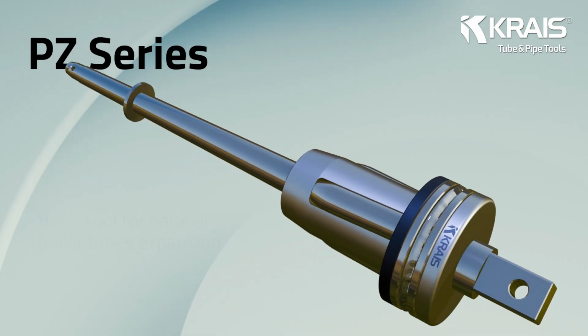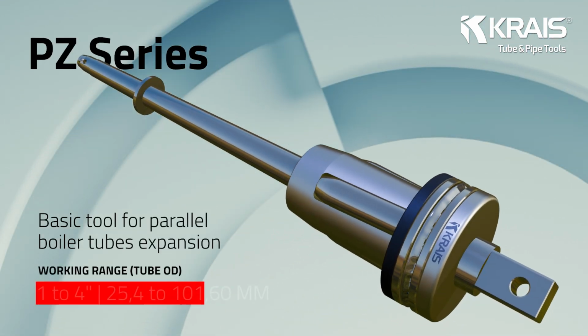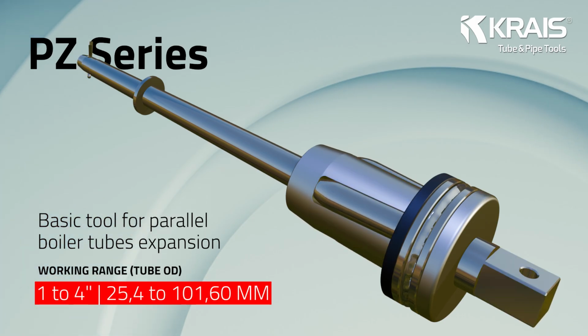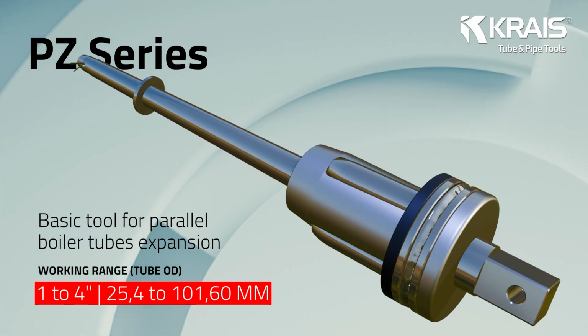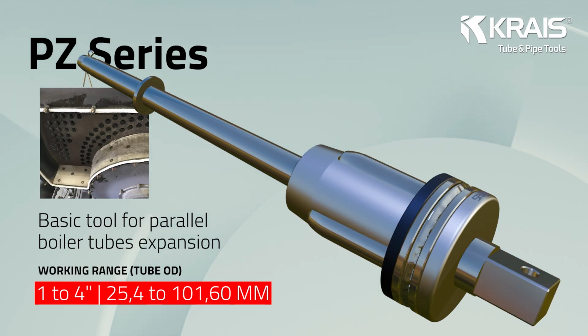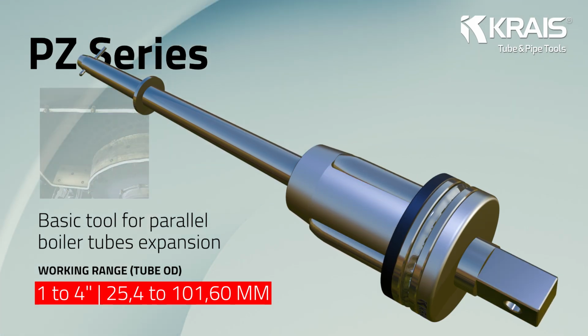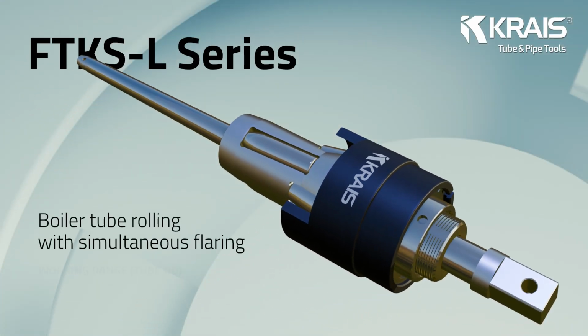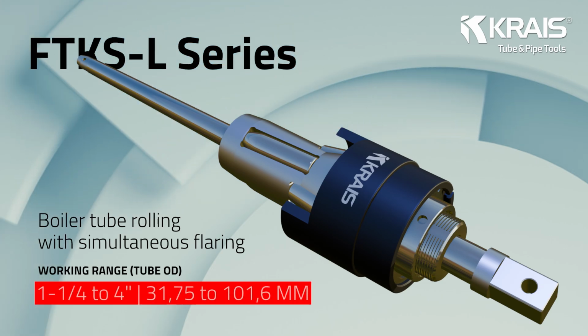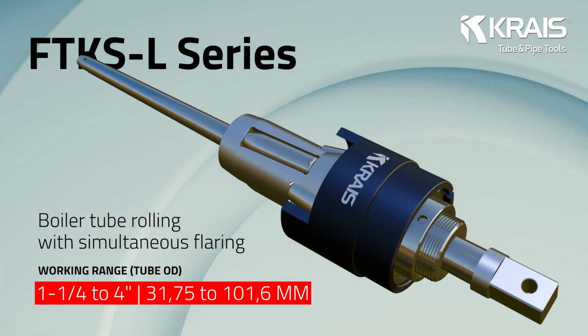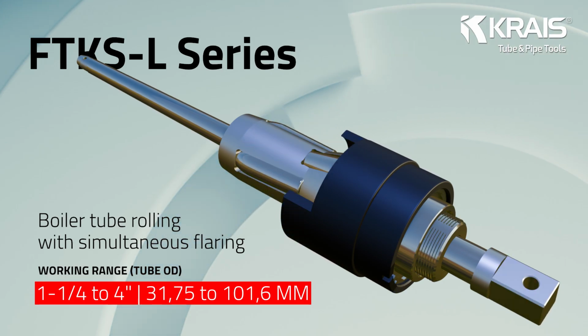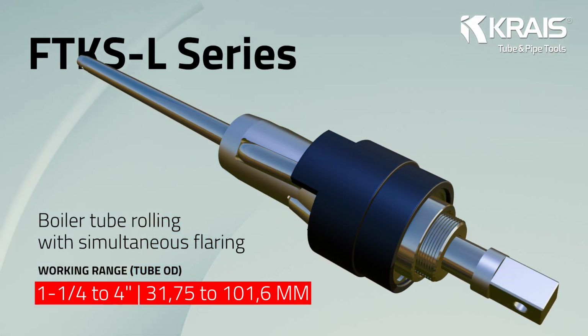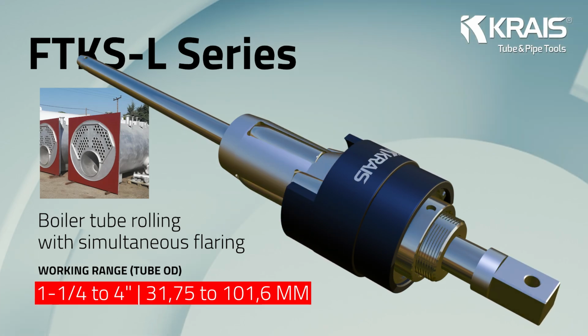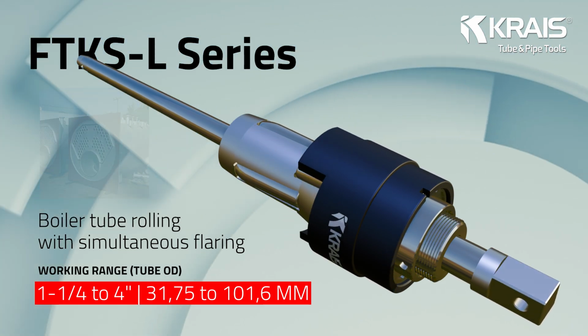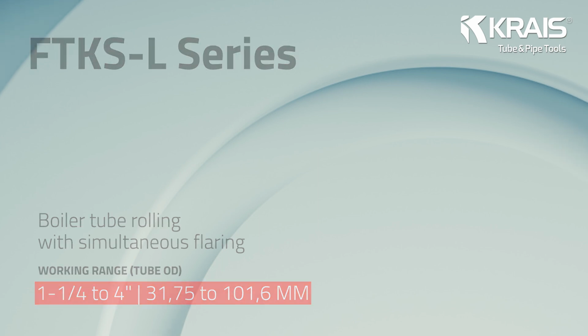The PZ series is the fundamental tube expander designed for basic maintenance and production of boilers and furnaces. This tool provides parallel rolling through an integrated thrust bearing and is engineered for expansion based on the specific length of the rollers. KRAIS FTKSL combines tube expansion with controlled flaring in boiler applications, using an adjustable stop to maintain consistent flare geometry across the tube field. This tool is recommended for less experienced boiler makers who may find simultaneous rolling and flaring with KS expanders challenging.